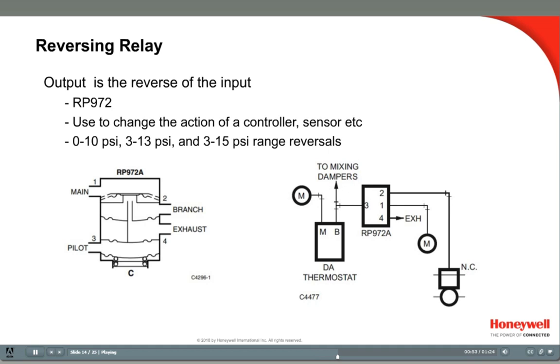In this example, a VAV box has a normally closed damper and a normally closed reheat valve. As the room temperature decreases, the direct-acting thermostat closes the damper to a minimum position. On a further drop in room temperature, the reheat valve should open. But it's a normally closed valve, so a decreasing pressure would close it — that's not what we want. So a reversing relay is used to reverse the branch line pressure to open the reheat valve on a drop in pressure.